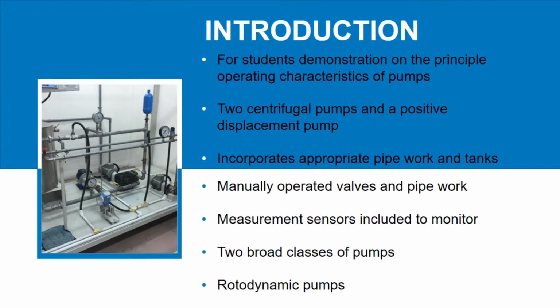Measurement sensors are included to monitor the pump speed, power, pump head, and flow rate. There are two broad classes of pump. Positive displacement pumps, which include gear pump, vane pump, and piston pump, have a fixed displacement of liquid per revolution. Rotodynamic pumps, which include axial pump, centrifugal pump, and mixed flow pump, generally work at a high rotation speed. The pressure difference between the suction and the delivery arises from the conversion of kinetic energy and pressure energy.